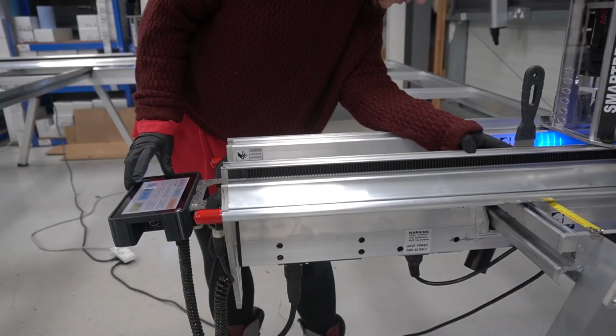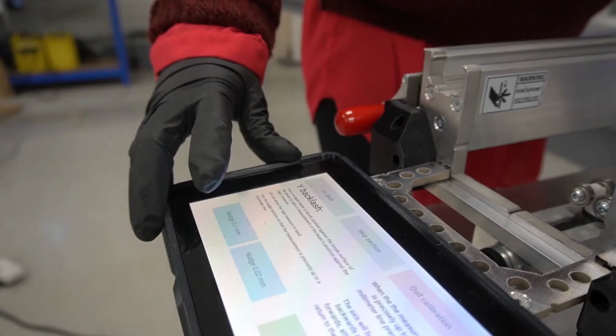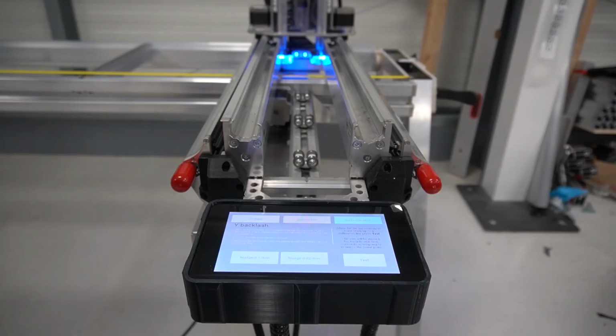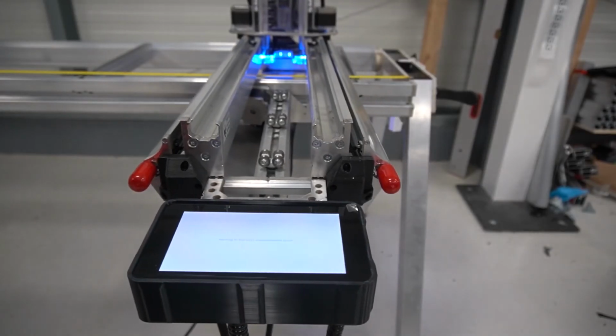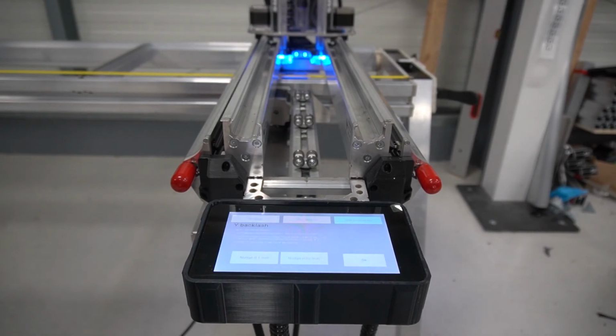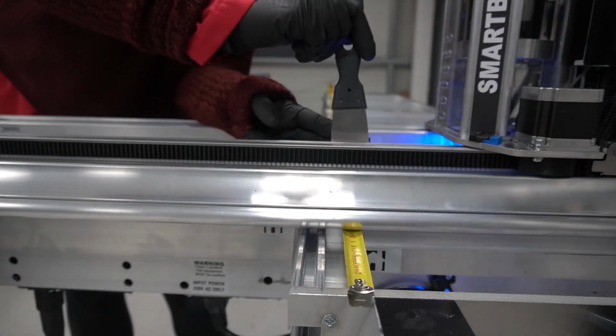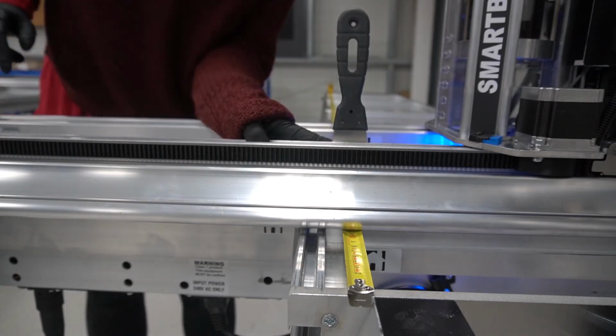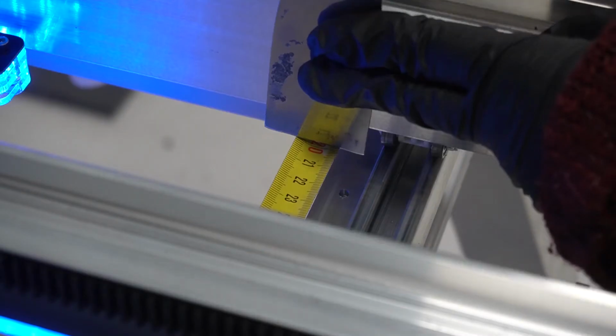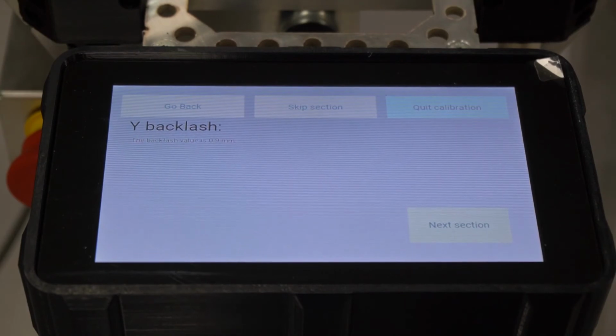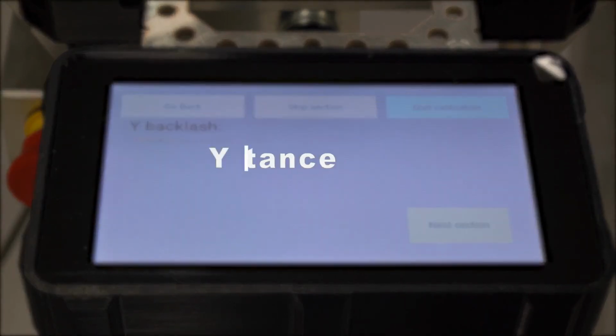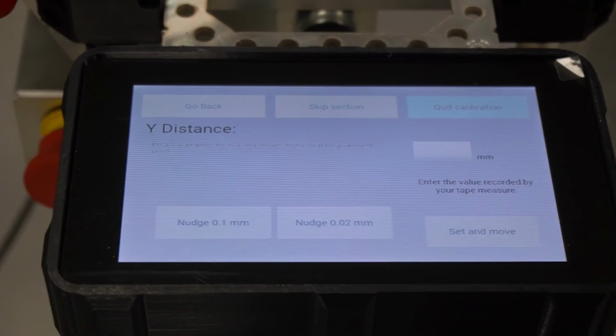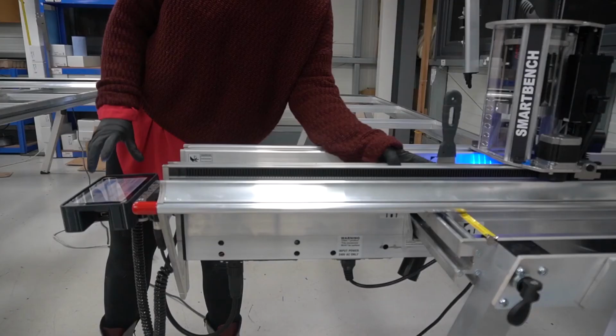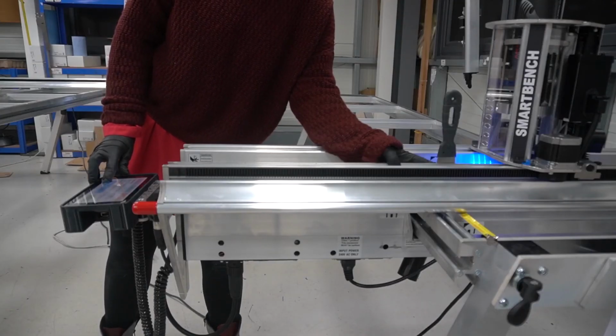Take your first measurement, using the nudge buttons to ensure you are precisely up to a millimetre line. Then press test. The axis will be moved backwards and forwards, attempting to return to the same point. Repeat your measurement, this time using the nudge buttons to return to the exact same position. Pressing OK will tell you the backlash value. Move to the next section and take a measurement as before, using the nudge buttons to ensure you are precisely up to a millimetre line.